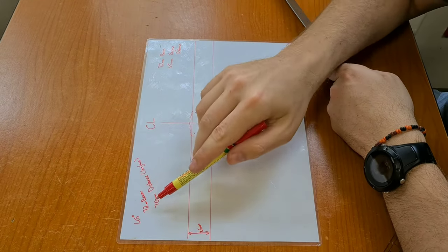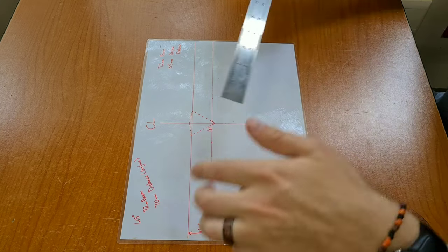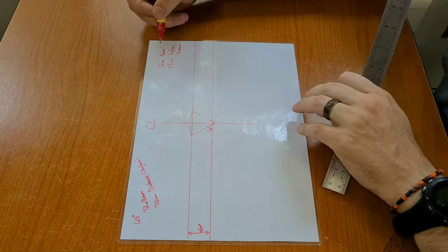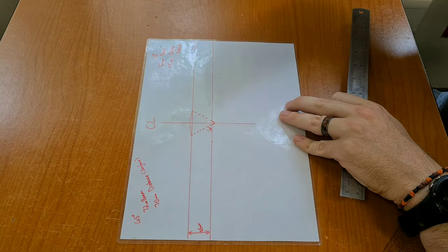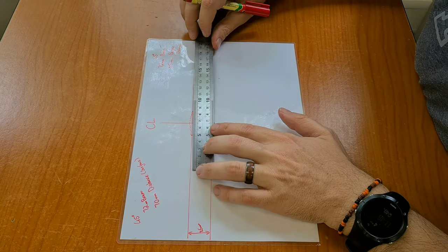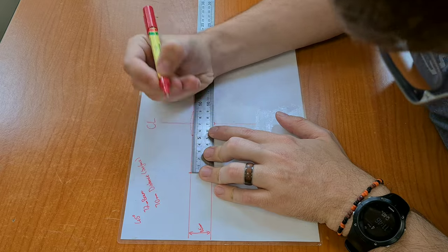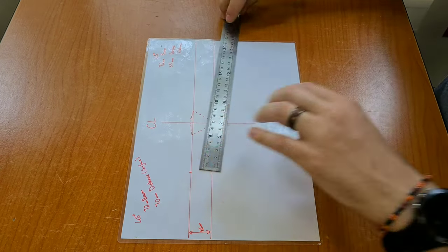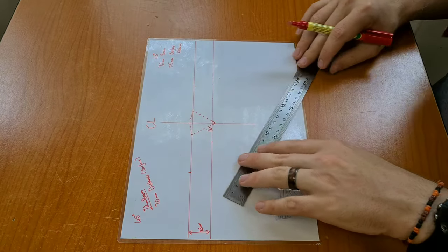All right, I've transferred the data to my drawing and we used the 45 degrees on both sides. Once again, this is a scale drawing of my weld if we were to cut a slice out of it. So I'm just going to draw in a 70 millimeter surface distance. So that's about 70 millimeters from the surface.